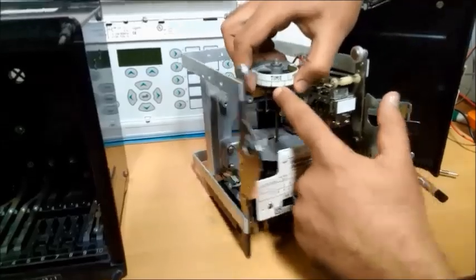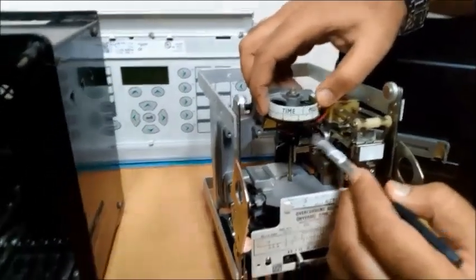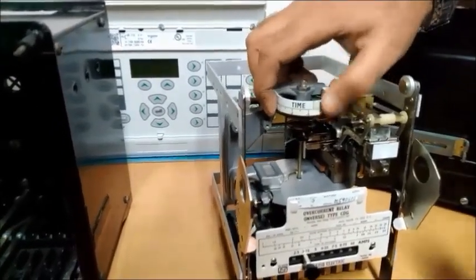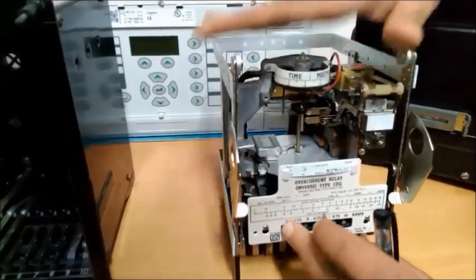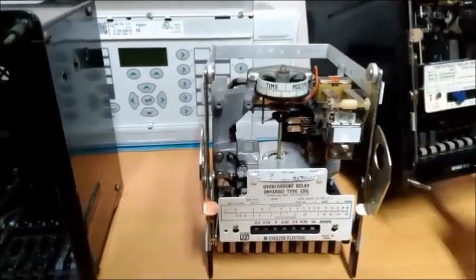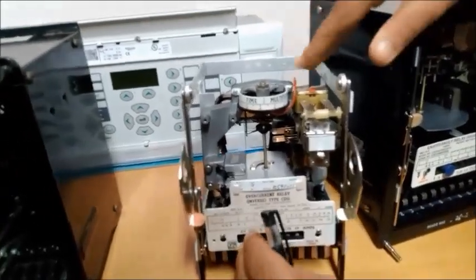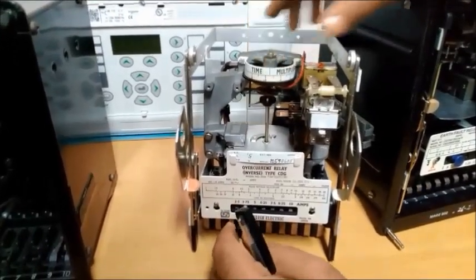So here you can see there is some value. You can see here. That is our time multiplier setting. That is TMS. Now we set already 0.3 seconds. And our current settings I already set here is 0.75 amps. So that is our set current settings and that is our TMS.